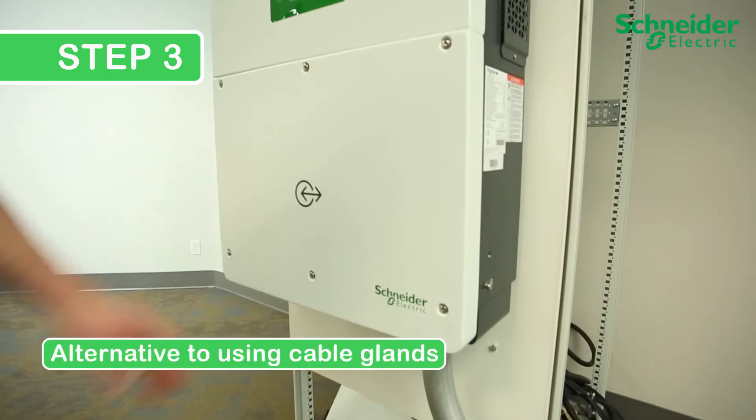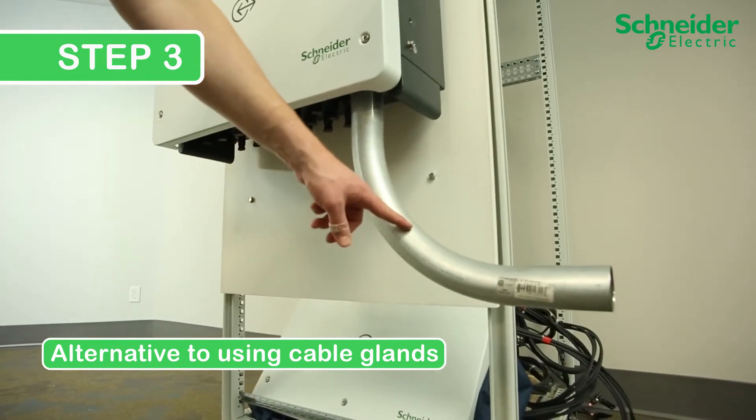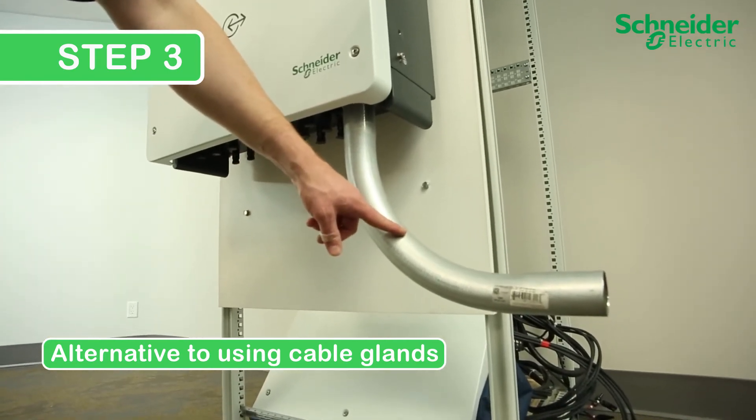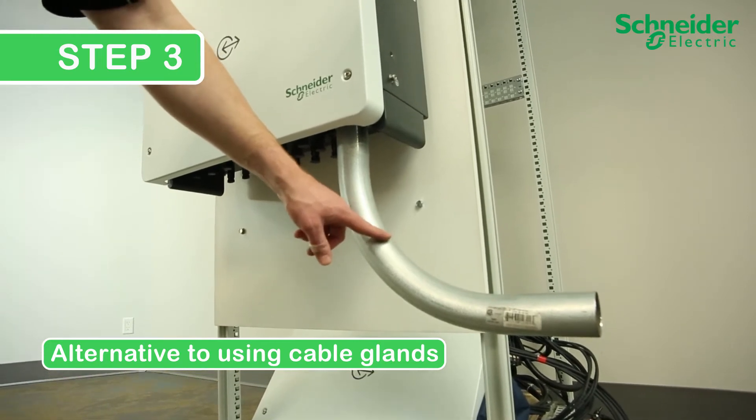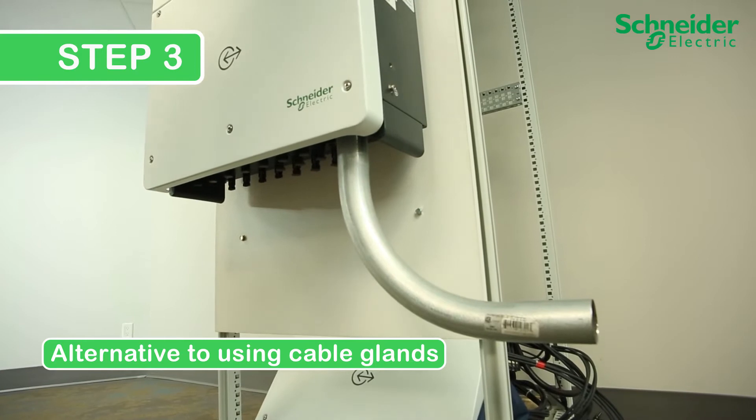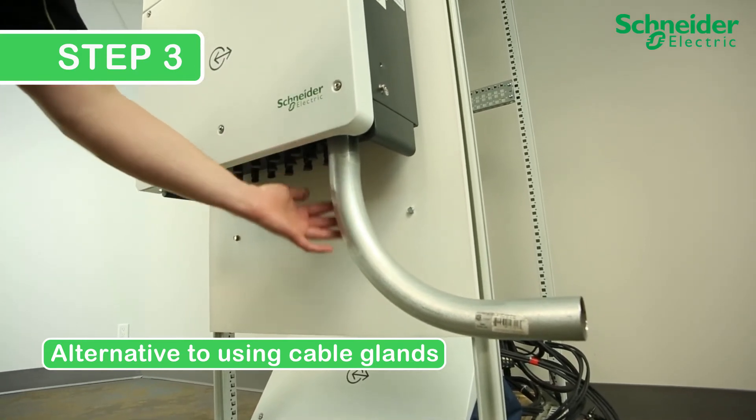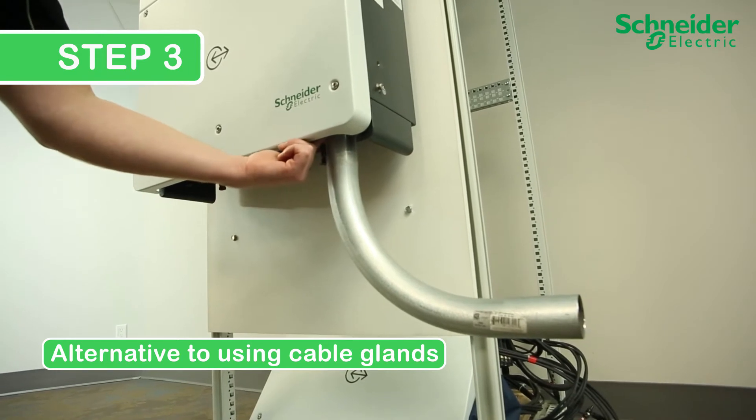As an alternative to using cable glands, conduit can be used with the CL60. There are different options in conduit types, and selection depends on your jurisdiction's regulations to meet proper installation requirements. Independent of conduit type, a weather-tight seal must be used with conduit to ensure that the IP rating of the unit is maintained.